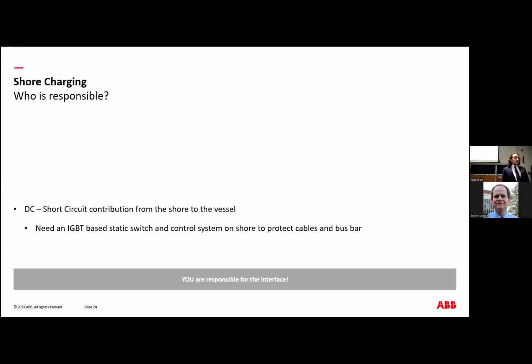Finally, for DC charging systems, the shore electronics that convert to DC provide power to the ship, and in the event of a fault on the ship, these systems also need to protect the ship—they need to prevent the fault from causing a fire, which requires that breaker, which in DC is typically an IGBT-based static switch component. At ABB we call this product an input circuit, but it's made by a few manufacturers worldwide and is very specialized—definitely something shoreside electrical engineers aren't familiar with. So for those three reasons and lessons learned, I'm recommending naval architects be responsible for the overall integration and ensure the electrical contractors are on the right path.